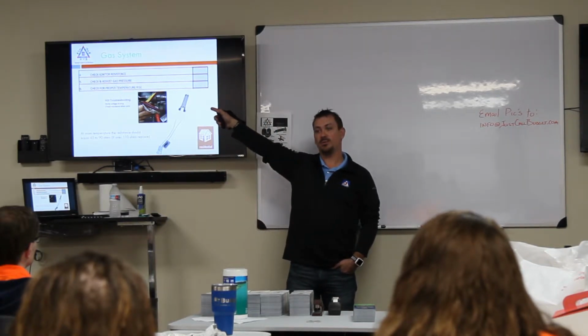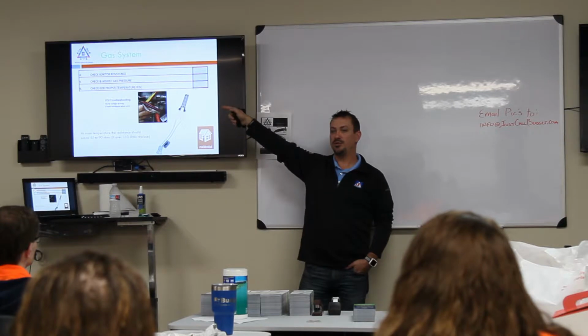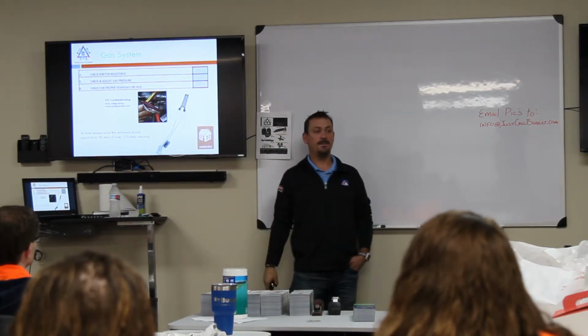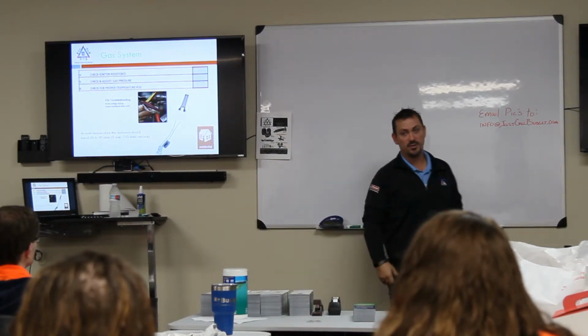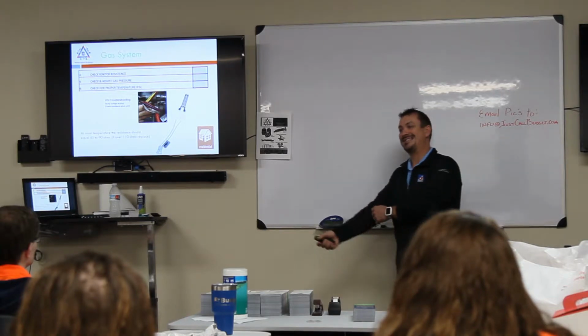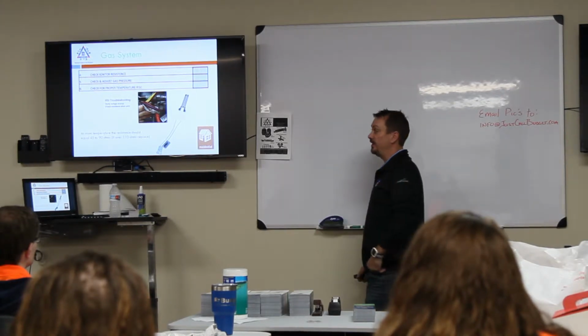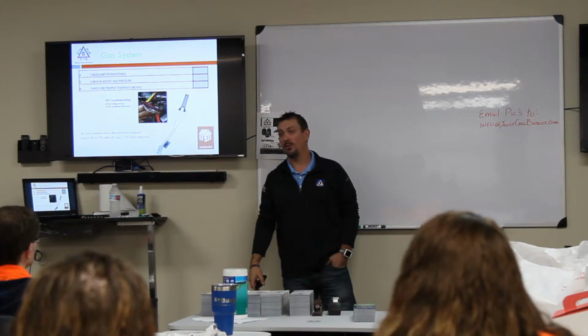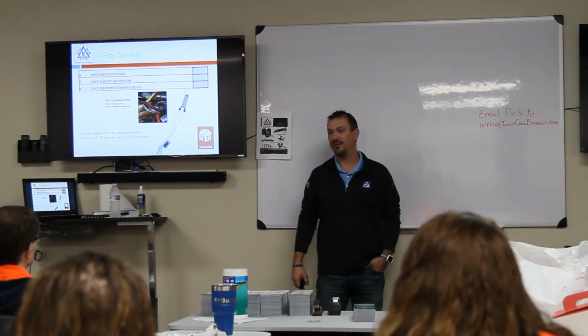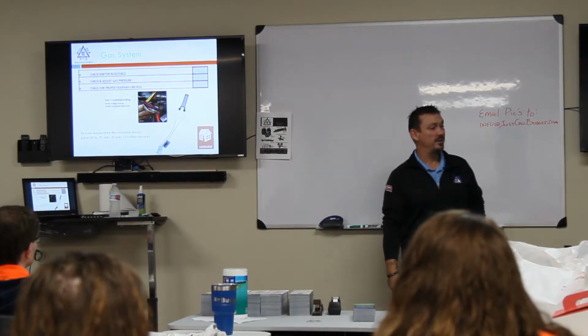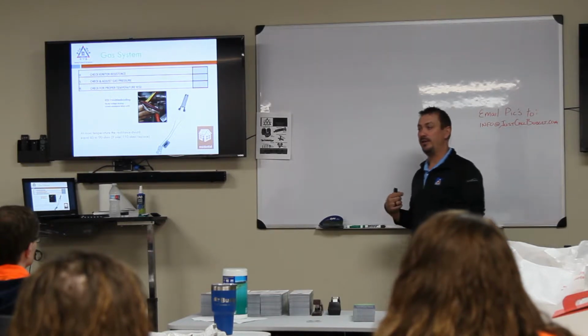Now, some myths on this one right here. The myth is do not touch the end of that igniter, because the oils from your hand will shorten the life of it. That is not true. That is a myth. Don't touch the end of it, because when it's glowing red hot, it's nice and hot and you'll burn yourself. And also don't touch the end of it because it's very fragile and it will break.